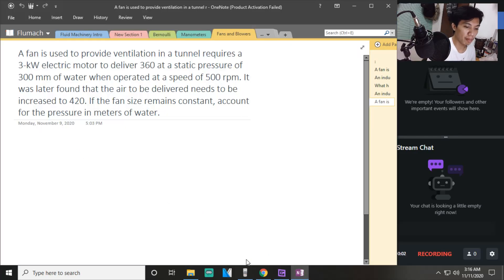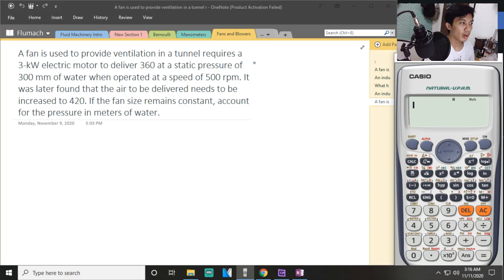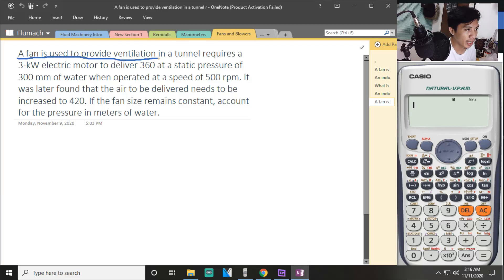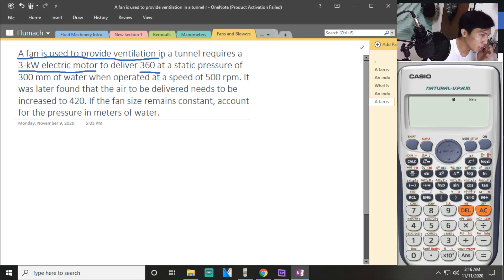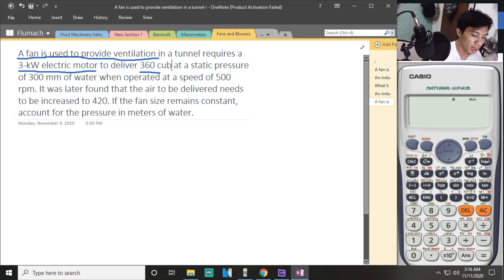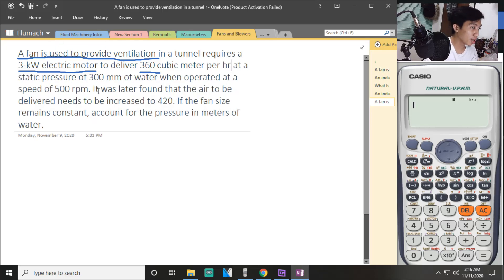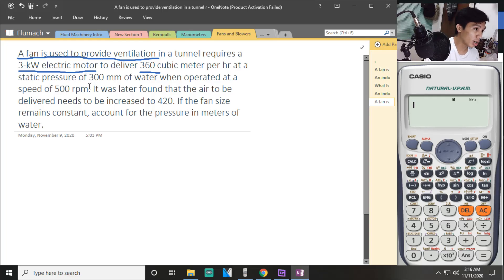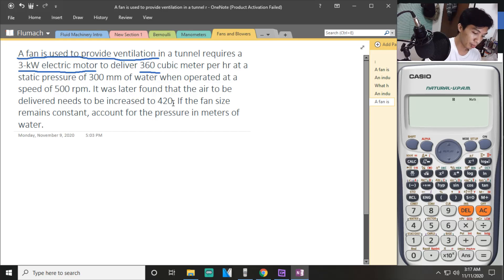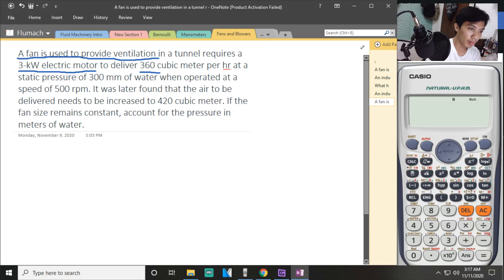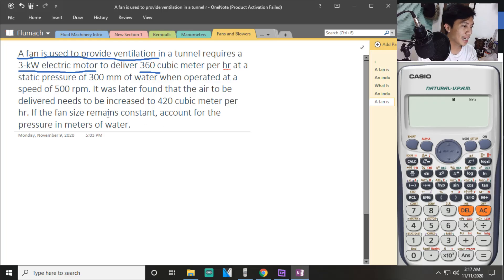For problem number five, a fan is used to provide ventilation in a tunnel. It requires a 3-kilowatt electric motor to deliver 360 cubic meters per hour at a static pressure of 300 millimeter water gauge, when operated at a speed of 500 rpm. It was later found out that the air to be delivered needs to be increased to 420 cubic meters per hour, with the fan size remaining constant.